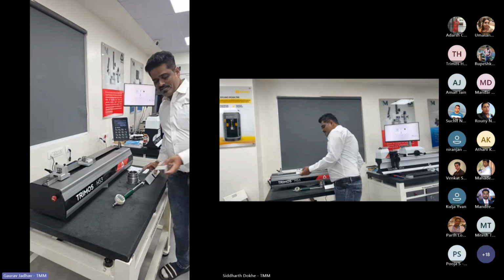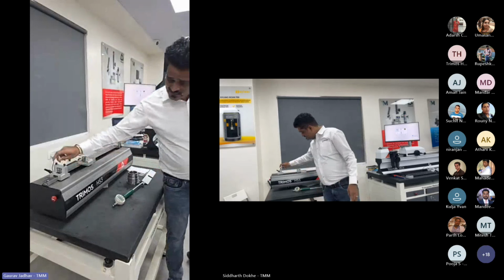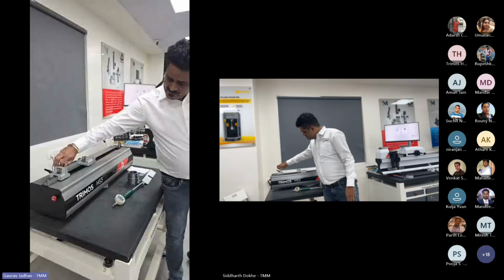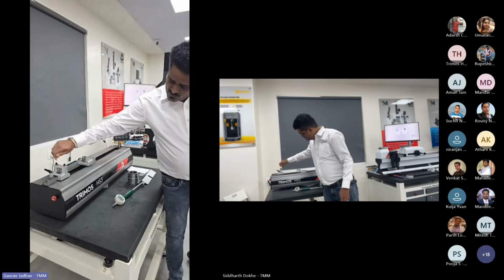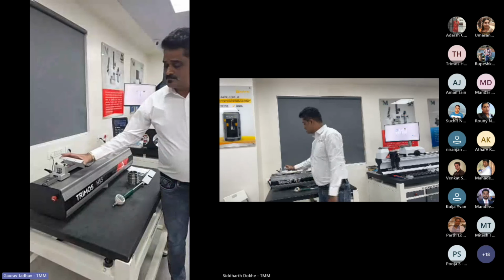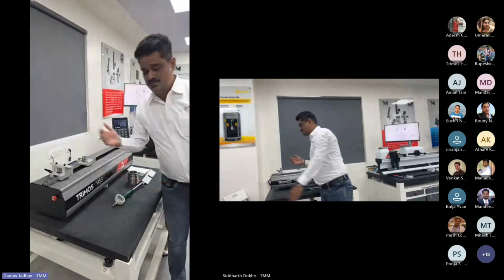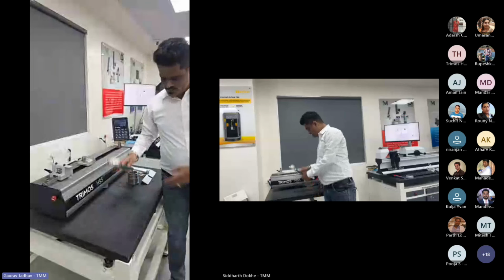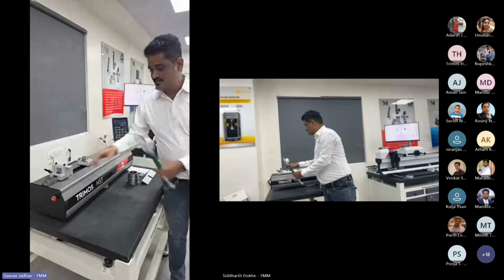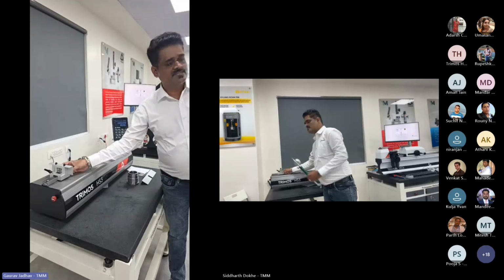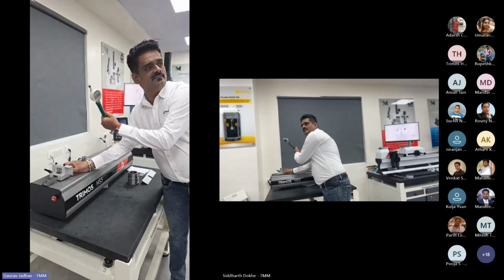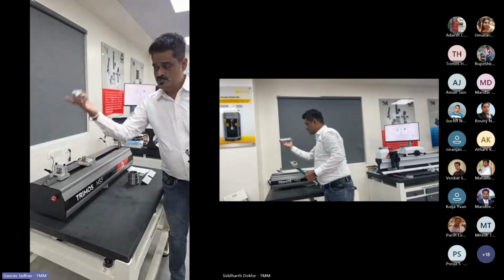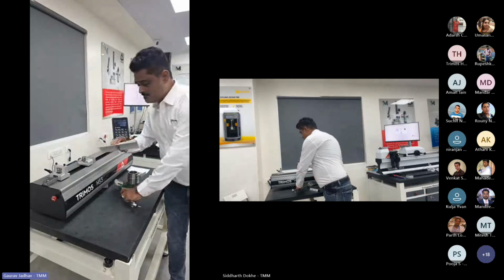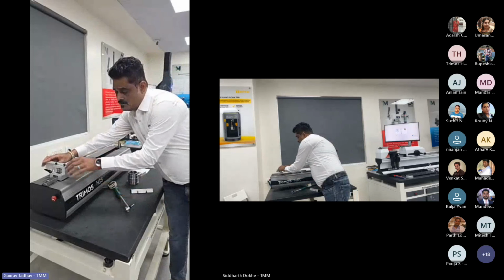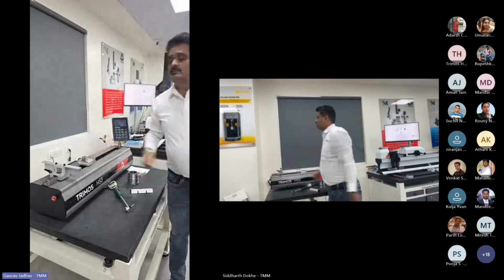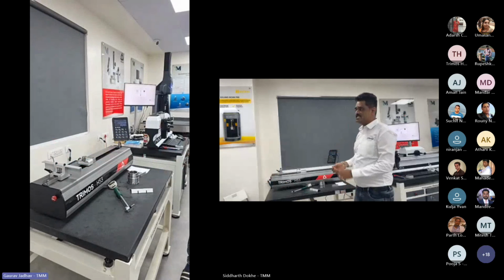The loading of this plate is very easy. If you can see this, there are two balls here and this is spring loaded. You can see these balls are spring loaded. Just you have to insert this plate here. It is very easy. Now this board, if you have a bigger bore gauge, this plate will support to rest your bore gauge and you can find the reversible point easily. Just like that, you have to remove this. You can fit the bigger one if you have a bigger bore gauge. It's very easy and quick setup.